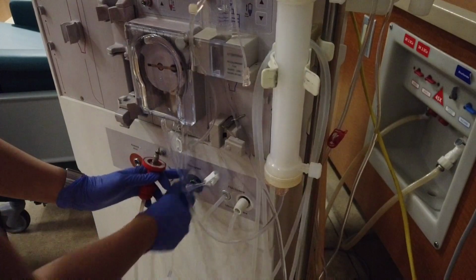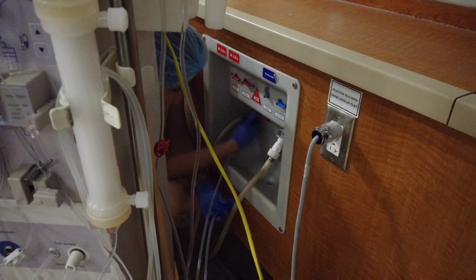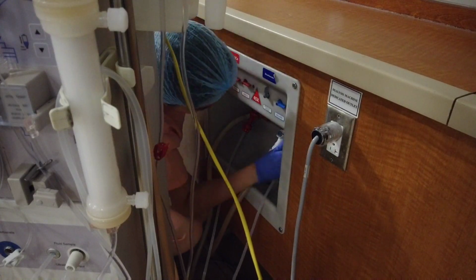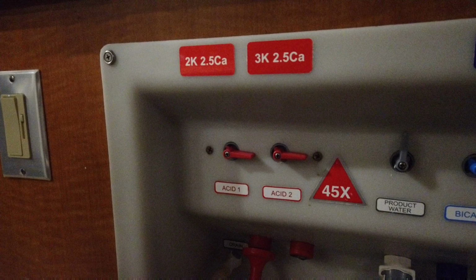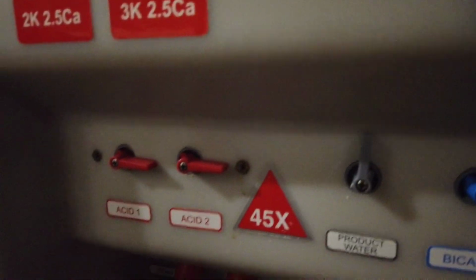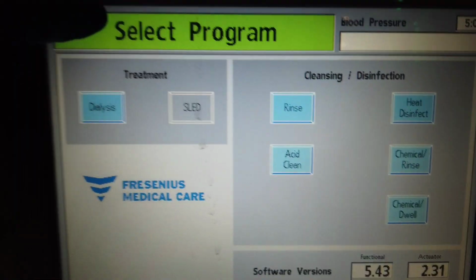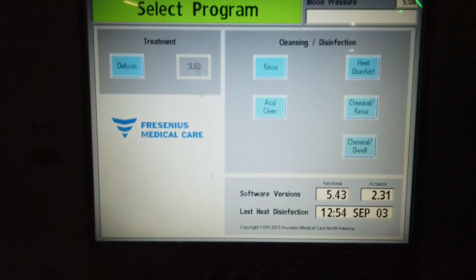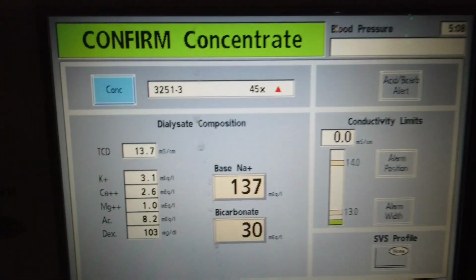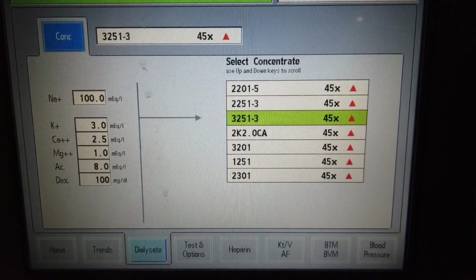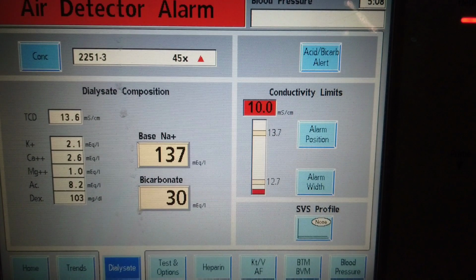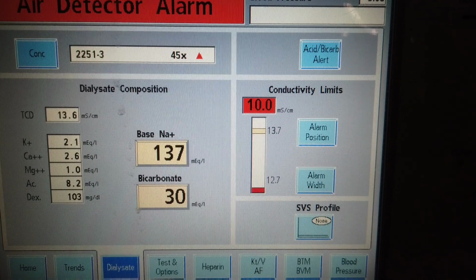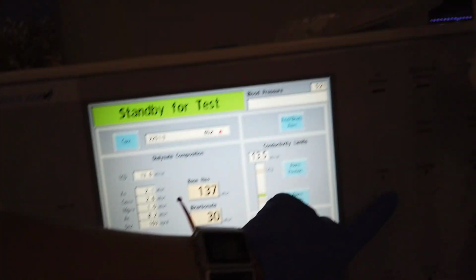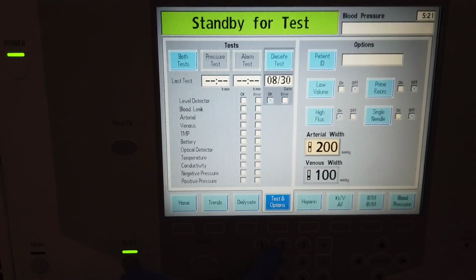Detach the acid and bicarb connectors from the machine and connect to the designated solutions. The widely used solutions are the 2K and 3K, which depends on the doctor's order. Simply turn it on by rotating the switch valves. Select Program on the screen by pressing the arrow buttons and press the Confirm button. Choose Dialysis. The machine will ask to confirm which concentrate. The ordered concentrate is 2251-3, then confirm. The conductivity limits will then appear, that is red initially, as it tries to load the concentrates. This will turn green once it is within the normal range of around 13 to 15.